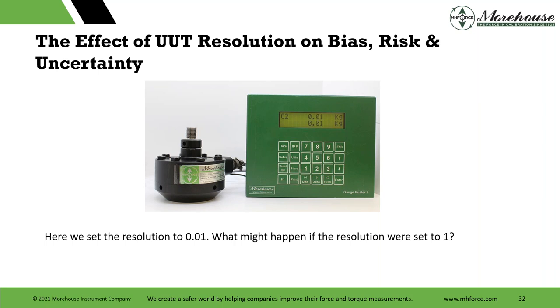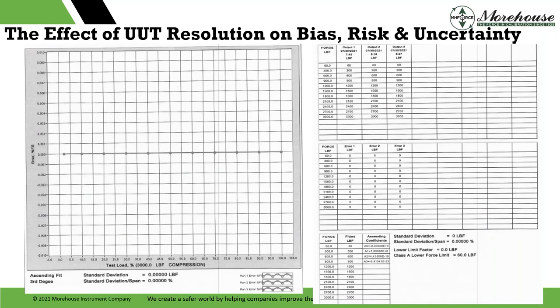This is a competitor — it shall remain nameless — but I have to call this to attention because it's exactly what happens when we have a coarse resolution: all of our measurements at some point become perfect, right? Standard deviation zero. Standard deviation to the span is zero percent. This is an ASTM cal, but everything's perfect — no error whatsoever. That one was set to a half-pound resolution on a 3,000-pound load cell — 6,000 counts. Very, very low.